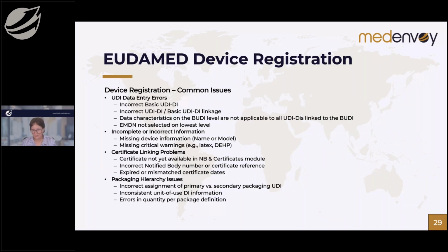So common issues identified during device registration that we have encountered so far, and that frequently happen, is that despite the fact that a basic UDI-DI is issued, even on certificates, when basic UDI-DIs are validated, and that is automatically done by EUDAMED, it is sometimes identified that the basic UDI-DI is in fact not a valid basic UDI-DI, so it has not been generated correctly. And in that case, you are stuck because you cannot upload your data, and you first have to resolve the issue, assigning a new basic UDI, and then update your documentation. So validate your data carefully as soon as possible.